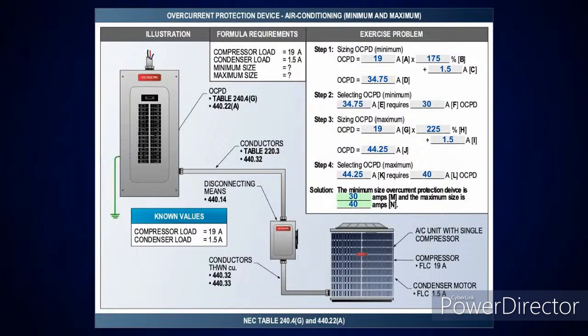Right. Okay. Now, one thing I want to point out here, I've done a ton of calculations so far. That rule of thumb I've taught up to this point: at 125% or less, go up to the next standard size. Anything above that percentage, you drop down, except for transformers where you have a superscript 1, and where you have phase converters for a fixed load and you're protecting the conductor, you go up to the next standard size. Everything I've shown you up to this point has held true, hasn't it?